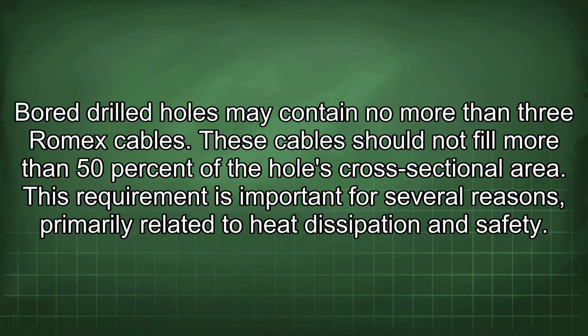Bore-drilled holes may contain no more than 3 Romex cables. These cables should not fill more than 50% of the hole's cross-sectional area. This requirement is important for several reasons, primarily related to heat dissipation and safety.